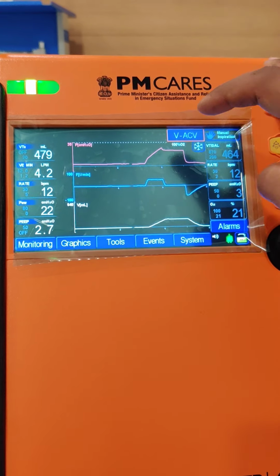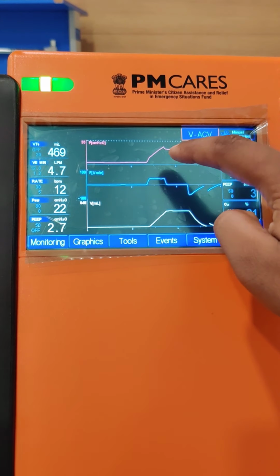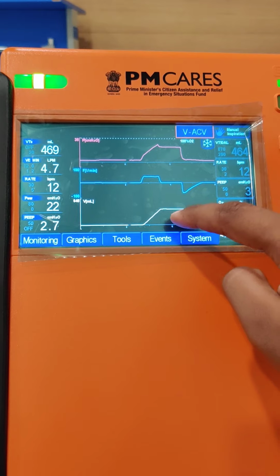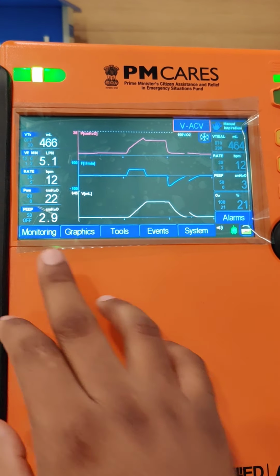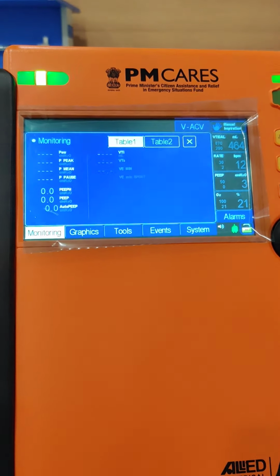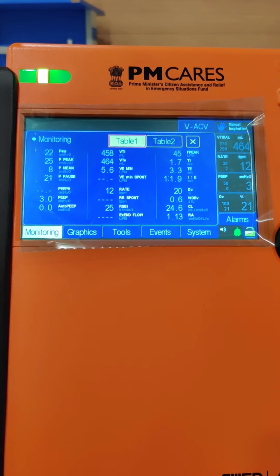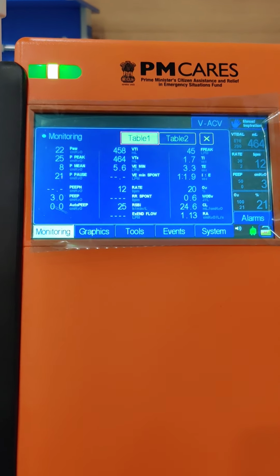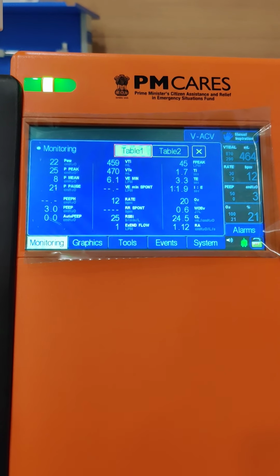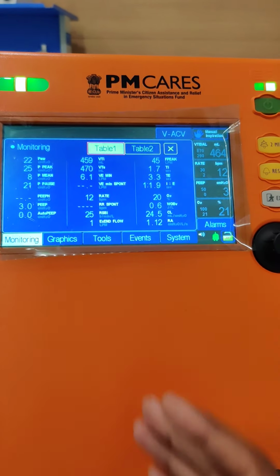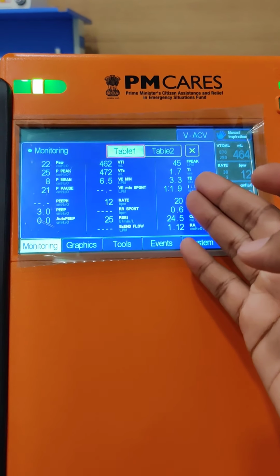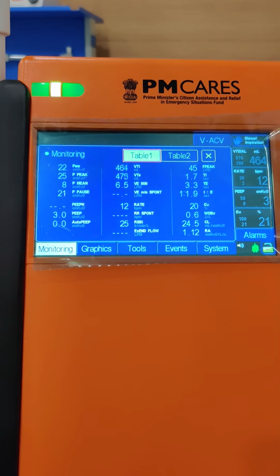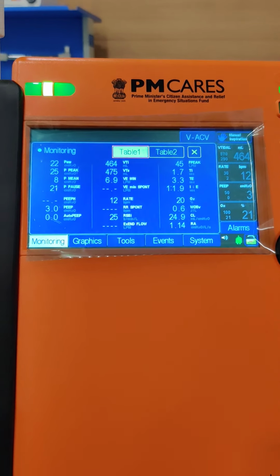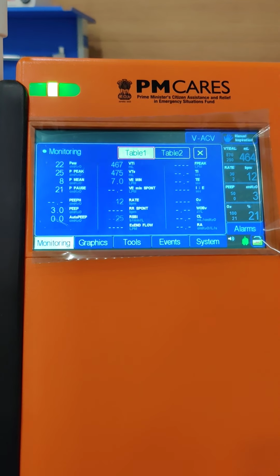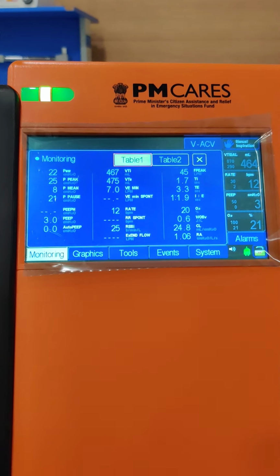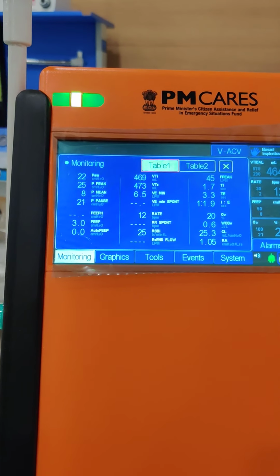Right now it is showing three waveforms: this is the pressure waveform, this is the flow waveform, and this is the volume waveform. First of all, if I go into the monitoring key, with a single touch of a button you will get all the detailed measured parameters on the display. These are the pressure parameters, these are the volume parameters, and these are the flow, time, and oxygen FiO2 parameters. You just have to touch this monitoring shortcut key, and all the parameters will be displayed on the screen.